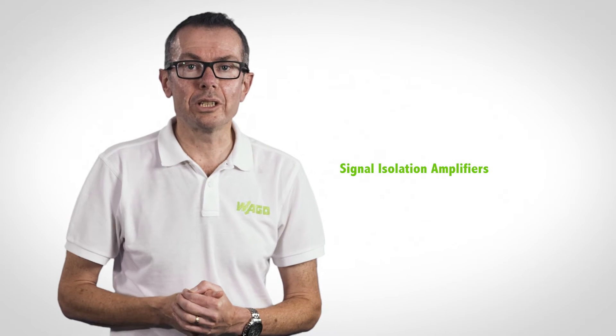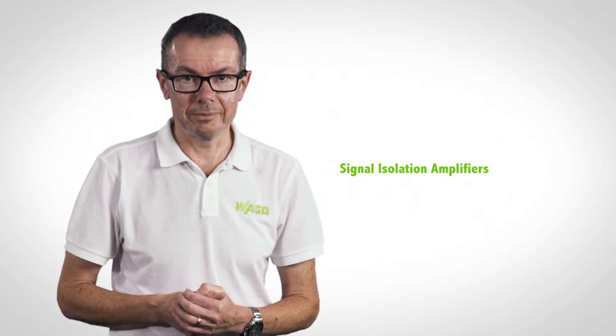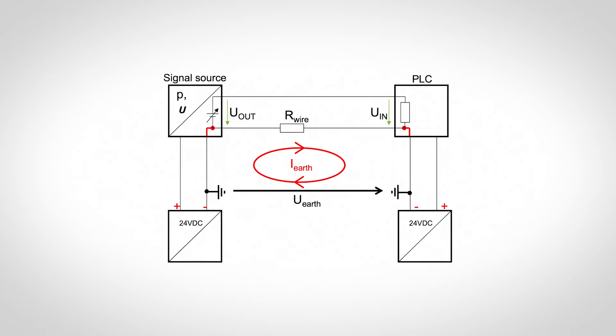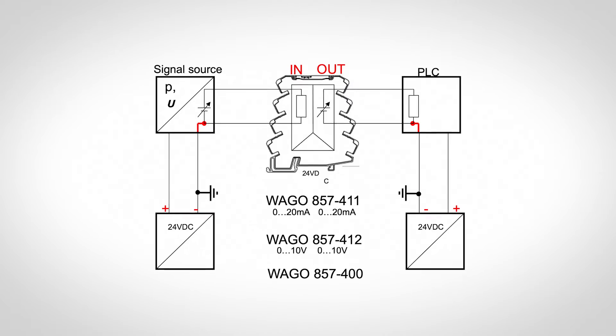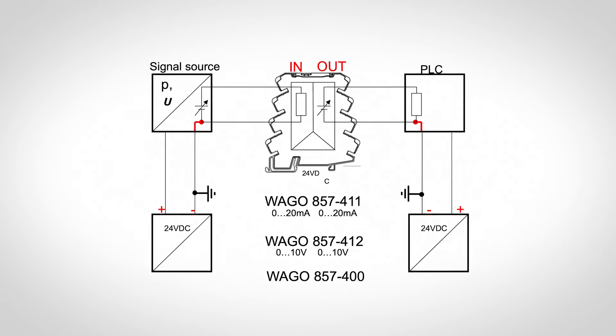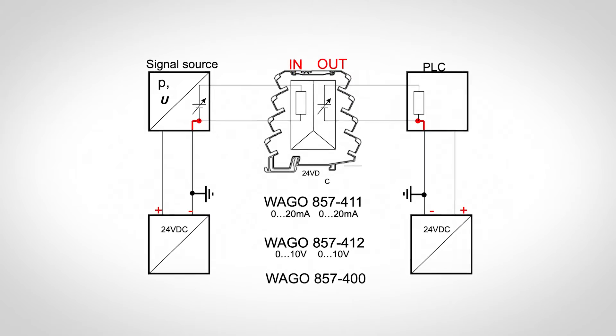Let's take a closer look at the various types. Signal isolation amplifiers: where two or more sets of equipment share the same DC power supply, there is a risk of a condition known as ground loops that can cause errors in signal measurements. By using signal isolation, this risk can be eliminated easily.